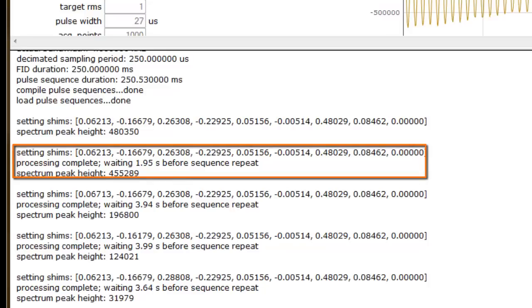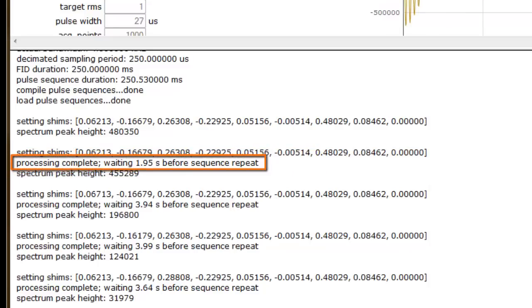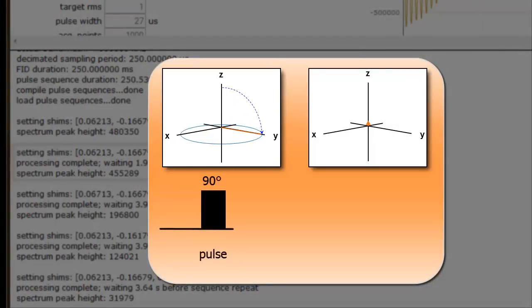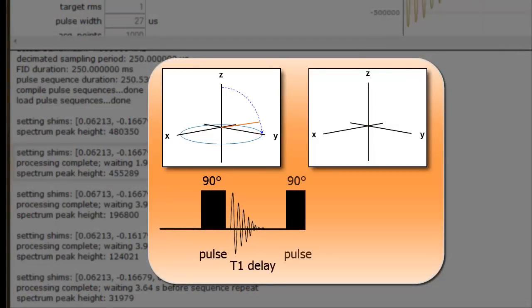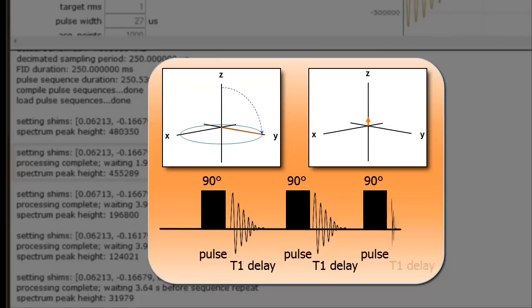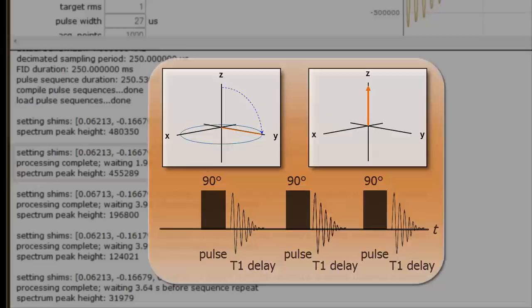The sequence of lines below this pair repeats the shim value and spectrum peak height information, but now includes a third line indicating that processing of data is completed, and that the script is waiting the remainder of the T1 delay before executing the next pulse. The time between pulses is determined by the T1 recovery delay, and all Fourier transform processing and data transferring from the instrument to the web browser user interface must be completed within the T1 timeframe.